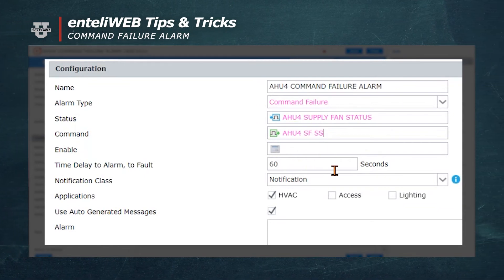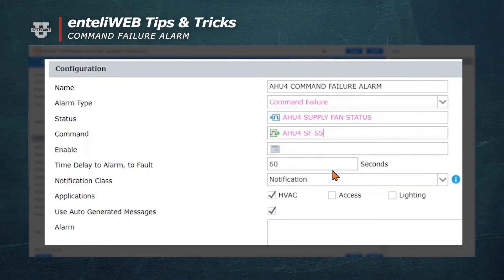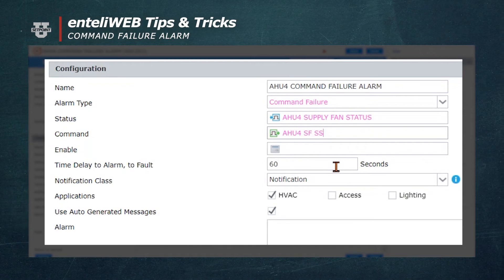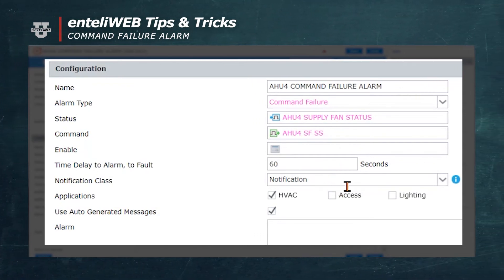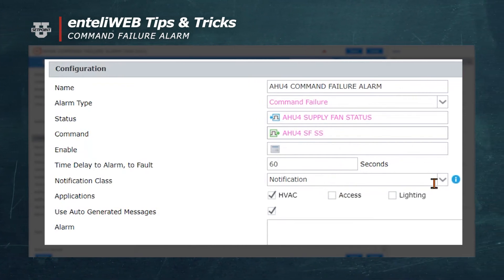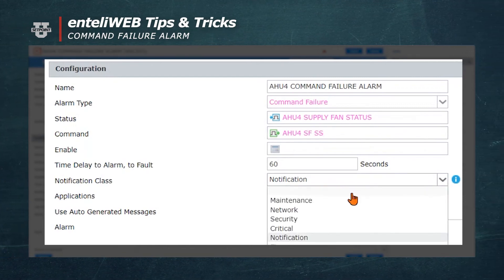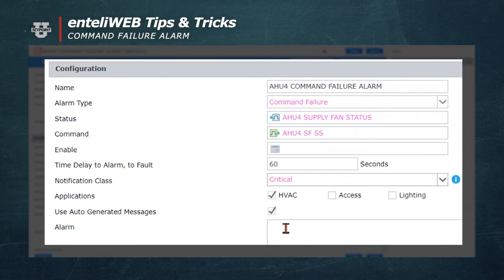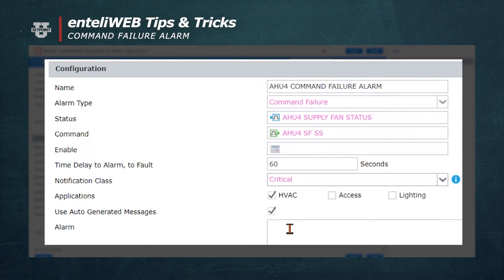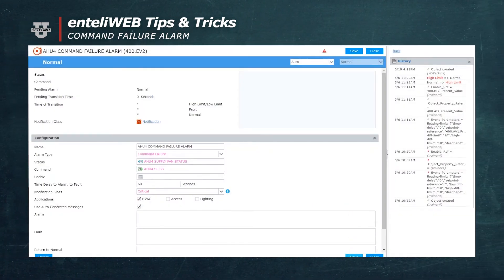There is a time delay of 60 seconds. Next we'll select notification class. Note that the default is Notification, which is the lowest class. We're going to select Critical so this alarm has priority over all other alarms when this equipment fails. From here we'll save this.